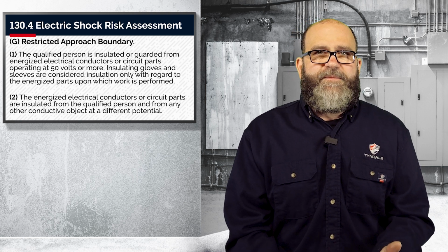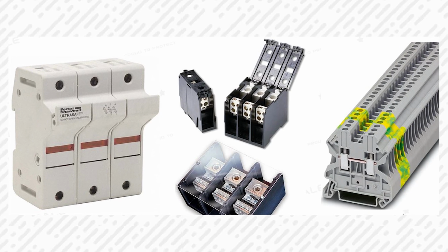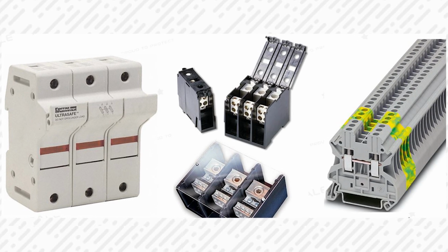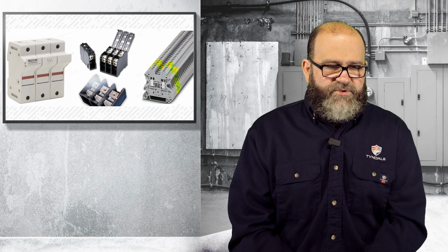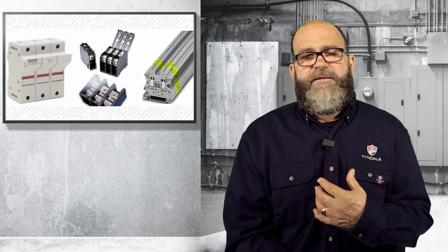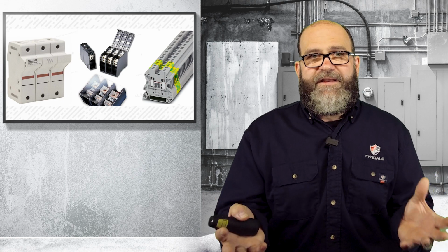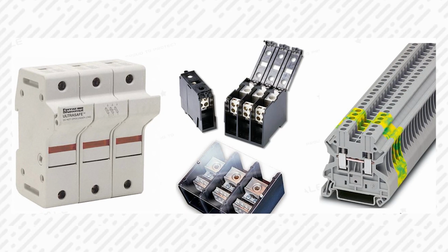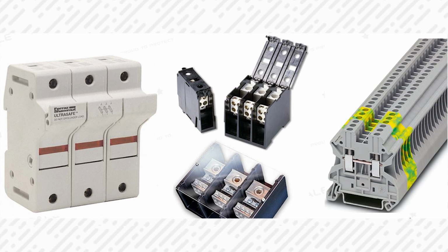So part of your job is to determine risk, right? And most of you have seen these types of terminations. It would be very difficult to contact live parts on the fuse holder on the left and the terminal block on the right, because the screws are buried in there. You'd have to be working really hard. So in my opinion, you may not need gloves within 12 inches of those 2 things, right? Whereas the guarded terminal blocks in the middle still have exposed parts that could be contacted.